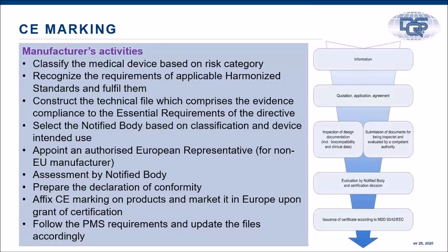And you need to construct the technical file which comprises the evidence of compliance to the essential requirements of the directive. I'll touch upon these essential requirements. Essential requirements are provided in Annex 1 of the directive. In MDD, it was called essential requirements. In the new regulation, it is called general safety and performance requirements. So that is what it has been renamed. But the basic concept remains the same in terms of demonstrating safety, performance, and effective performance of the device.